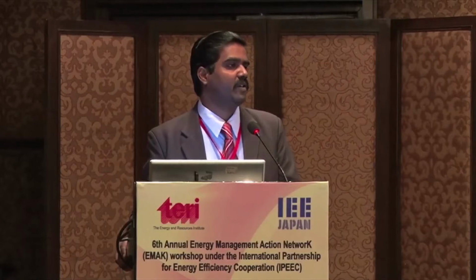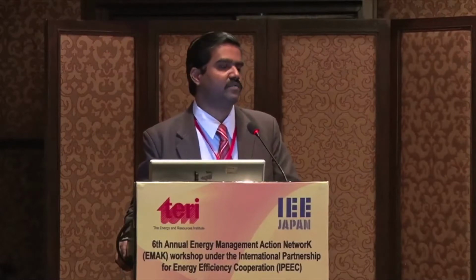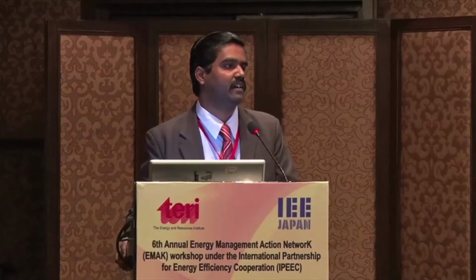With this hammering system, if we use heavy force, then normally the tubes may break. But if you use less force, then again the dust will not get removed, and within a short duration of time your heat transfer will reduce, and ultimately your power generation will be much lesser than what you designed. So that has to be taken care of. That is why, though it may seem very simple, this hammering system is a very critical design.